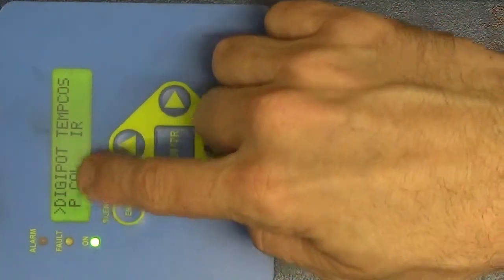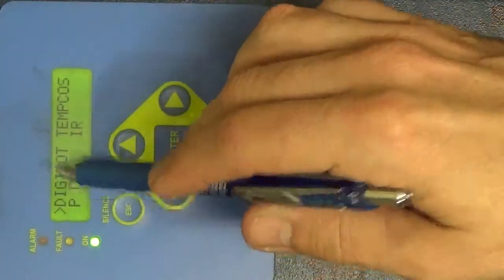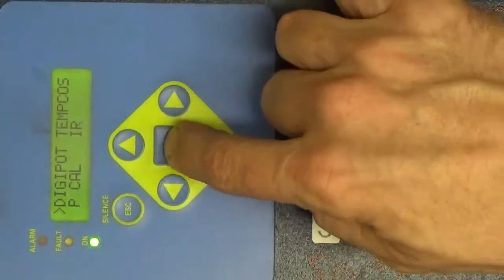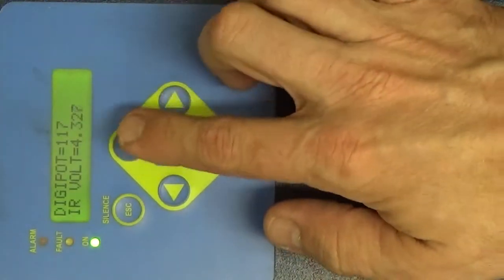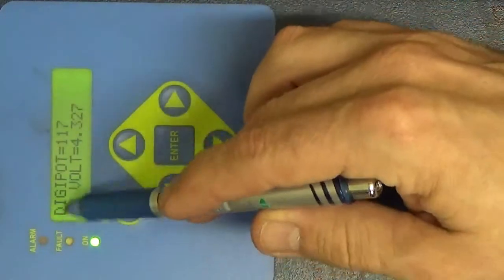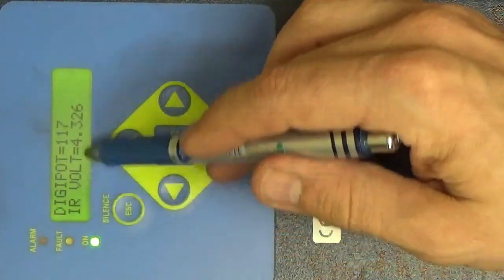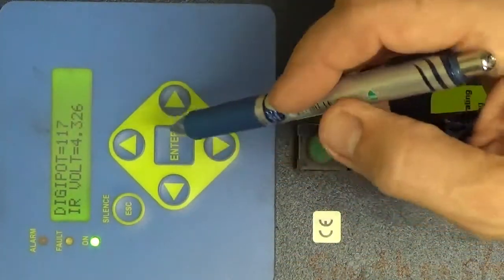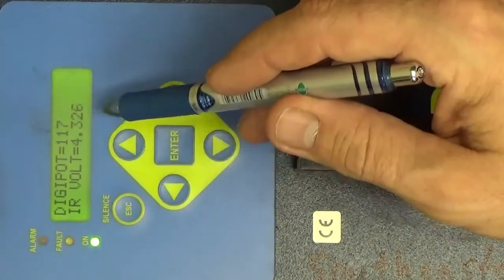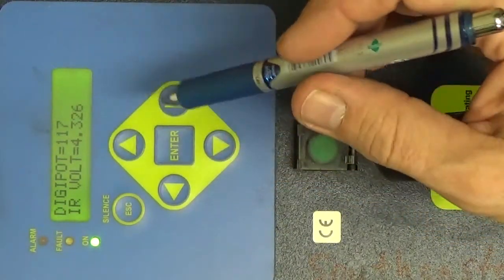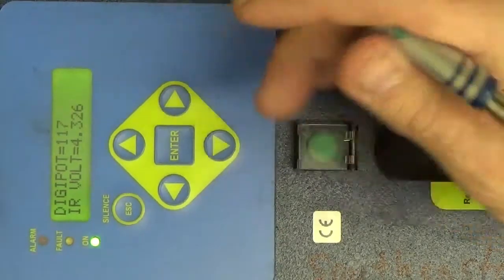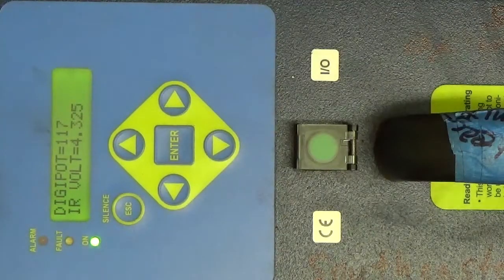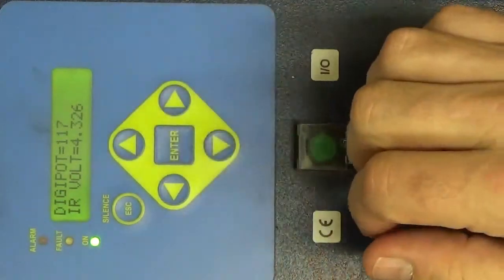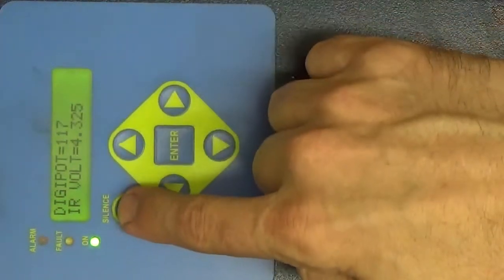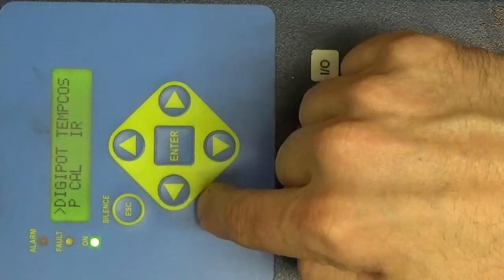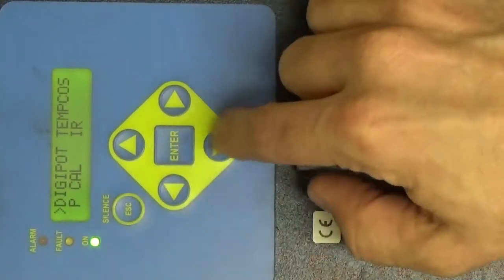So first thing we want to go into is something called Digipot. It's the first thing you come to on the second level. Hit enter, and all we want to do is record the numbers that we see here. We're going to see something called Digipot and something called IR volt. We want to record what the IR volt is at this current time. This particular one says 4.326, should be 4.2. So after we finish the calibration we're going to come back here and adjust those numbers. Right now we're just recording what's here. So hit escape to get back to our menu.